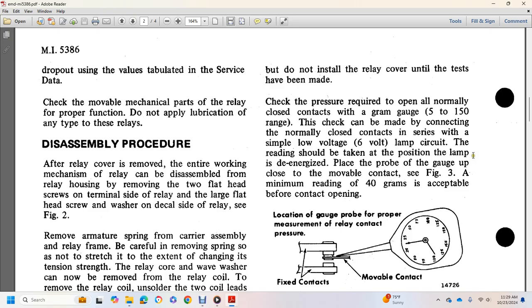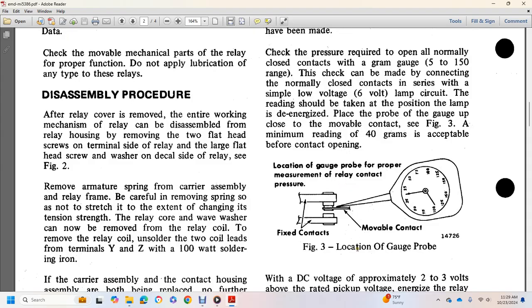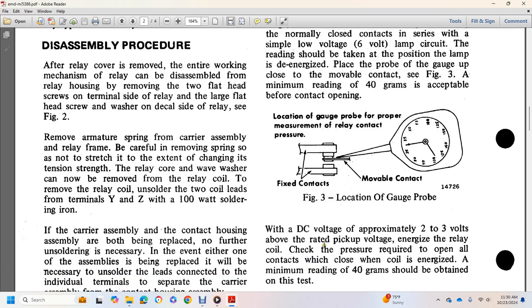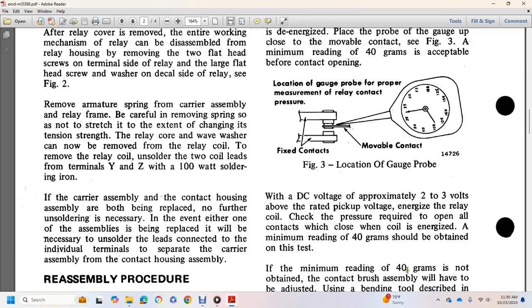Reading should be taken with the position of the lamp. is de-energized. Place the probe with the gauge up the close with a movable contact. See figure 3 with a minimum reading of 40 grams acceptable before contact opening. Figure 3 shows the location of gauge probe, fixed contacts, movable contact, location gauge probe properly mesh for the relay contact pressure. DC voltage approximately 2 to 3 volts above the rated pickup voltage, energize the relay coil. Check the pressure required to open all of the contacts closed with the coil. is energized. A minimum reading of 40 grams should be attained with the test.